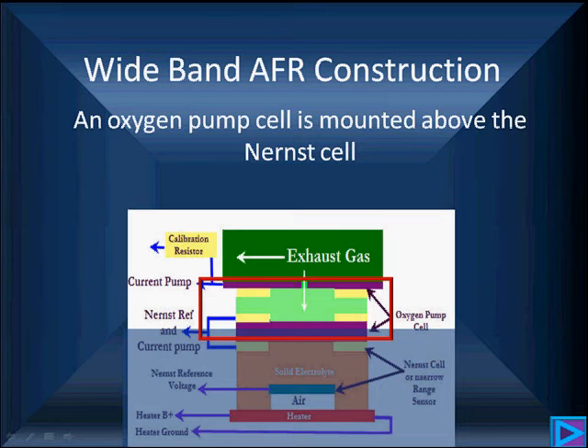If we're only allowing a small amount in, we have an oxygen sensor pump. It's that shared cell in the bottom with blue. We've got that blue cell on top. Now what happens with this? It's a standard narrowband cell, but something unusual happens to narrowband oxygen sensors. If you drive current in and out of them, they will absorb and release oxygen.